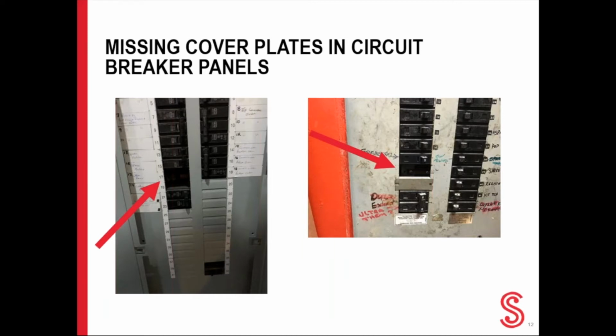So why is this important? Let's take two examples here. One, let's just say the lights went out and an employee tried to flip the breaker box back on, and their fingers just accidentally went through that little gap. This is just a bodily injury waiting to happen. The other one would be in regards to the property side. If the power was to go out and there was a surge, the sparks, again, could ignite nearby combustible boxes that were left around the breaker box.